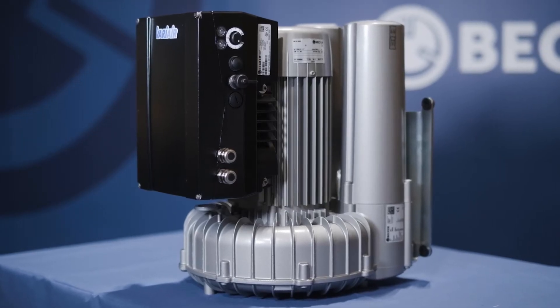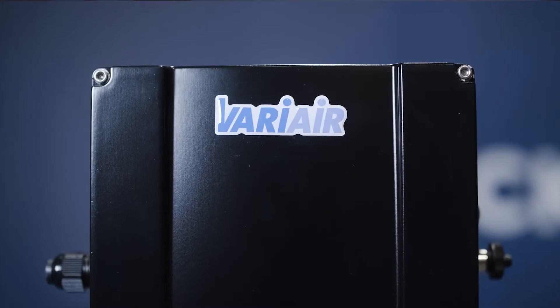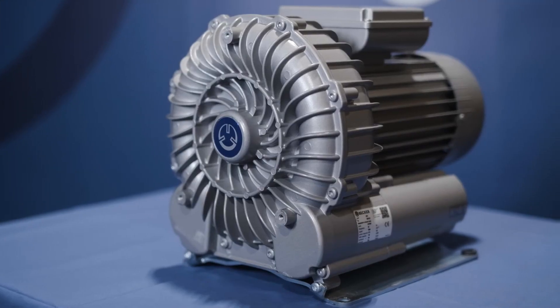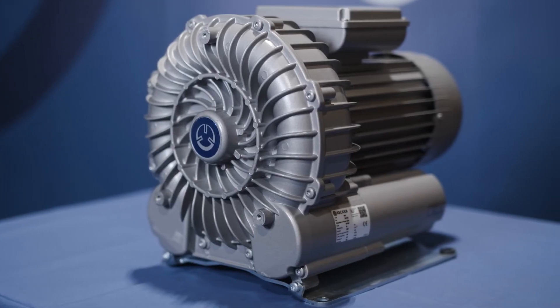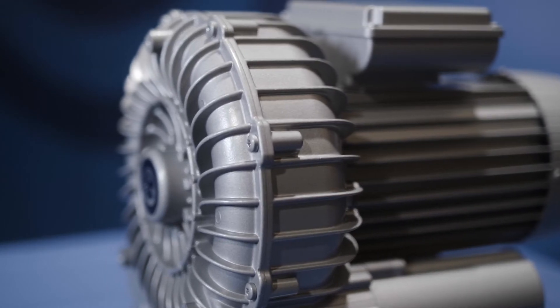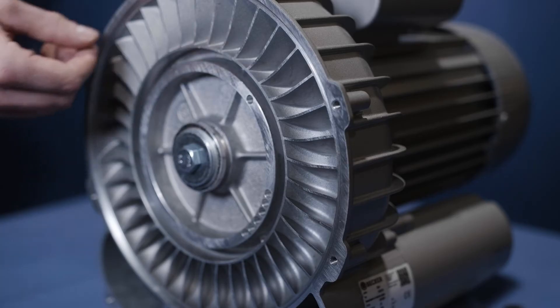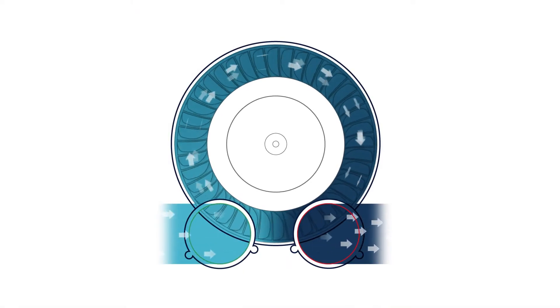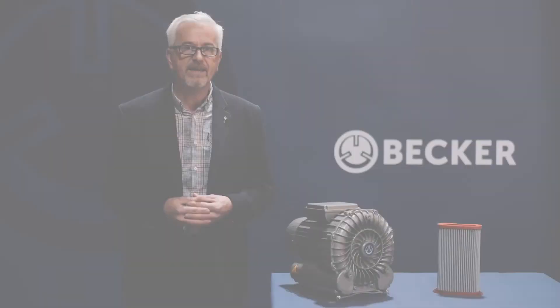Today I'm going to focus on the side-channel blowers from Becker. But firstly, what is a side-channel blower? Side-channel blowers are ideal for moving large volumes of air efficiently at low pressures or vacuum. The side-channel blower uses a bladed impeller which is enclosed in a housing but attached to a rotating shaft. The inlet and outlet of the blower are perpendicular to the rotation of the impeller. Air flows into the blower through the inlet port and is pushed around the housing enclosure by the impeller blades, and is then exhausted through the outlet port.